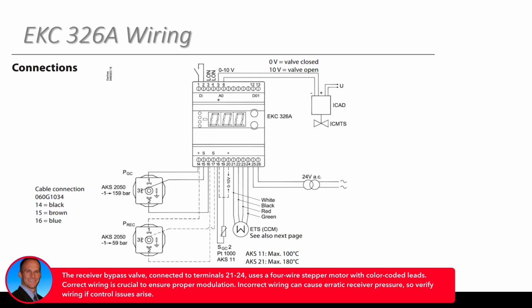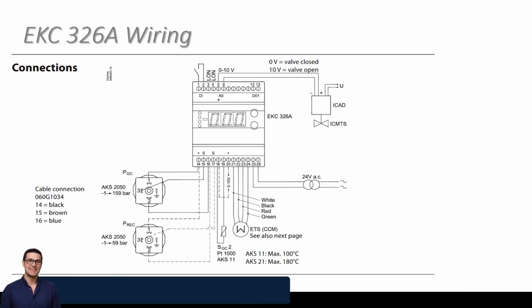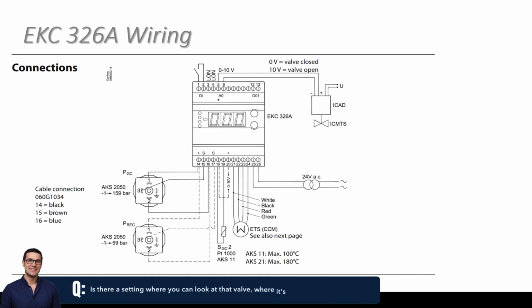That potentially it's supposed to be closing, but now it's opening when it says it's supposed to be closing. And will you see that on the screen as well? So the screen's going to say I'm 100% open. Is there a setting where you can look at that valve, where it's at in the controller? Yeah, there is. There's a parameter, that up here.